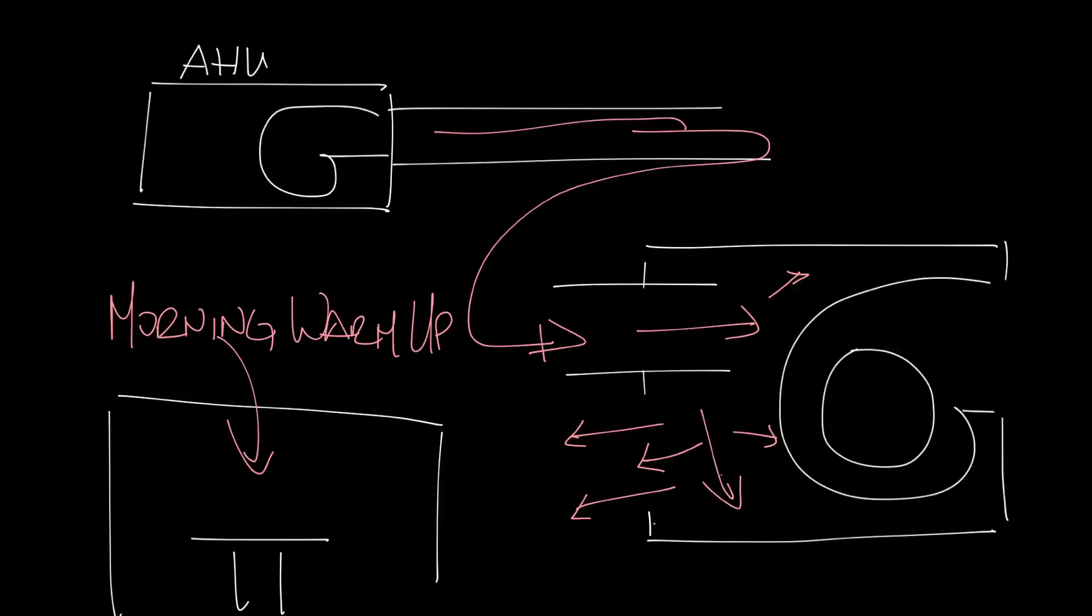Plus the positively pressurized inside of the fan box will likely cause the blower to start rotating backward. So what you'll eventually end up with is a warm ceiling plenum, not a warm space, and a fan box blower that's rotating backward.